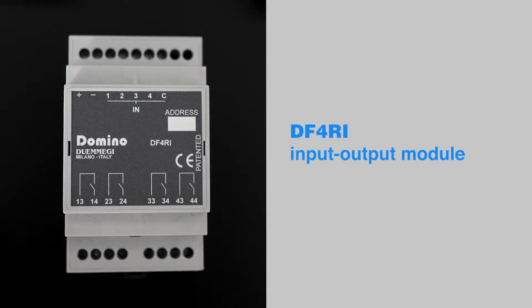The DF4RI module includes the following functions: 4 digital inputs for contacts without potential, 4 power relay outputs, which can be configured either for the on-off switch of generic loads or in couples for the control of rolling shutters and Venetian blinds, 4 virtual points for generic use.